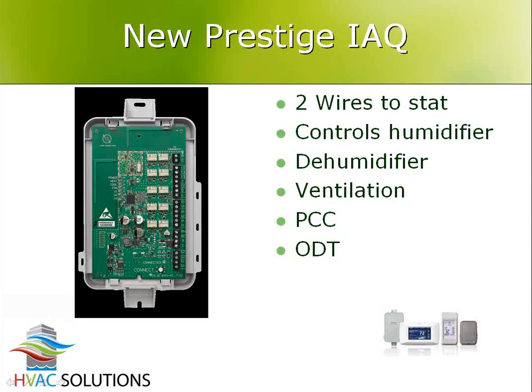He does not require any wires between the furnace and the stat. However, the stat does require 24-volt power. So I can either have 2 wires going down to the furnace to steal his power like I would on a normal stat, but just those 2 wires and no other wires needed. Or I can get a separate transformer and steal power from a closer source, from a 110 source or somewhere else. Right? So it's a 2-wire stat in that regard, which is nice because now you can retrofit it on any other stat application that you have.